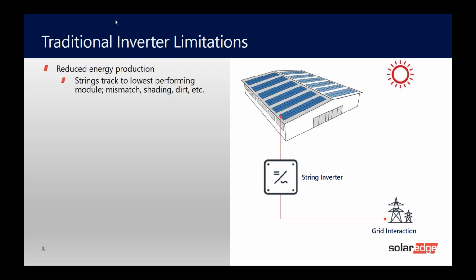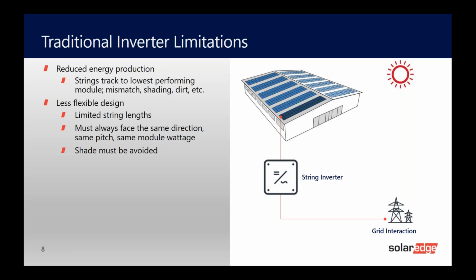So if one module is shaded, or gets a lot more dirt, say from birds flying overhead, sometimes soiling is very uneven, that single module limits the energy production for the entire string. Even with multiple power point tracking, you're still being limited by the string, that doesn't change. We can produce more energy because we put optimizers on those modules, which allow them to buck and boost and create a fixed string voltage of 850 volts. Those modules are helping out their neighbors, and you get the maximum amount of energy that system can produce.